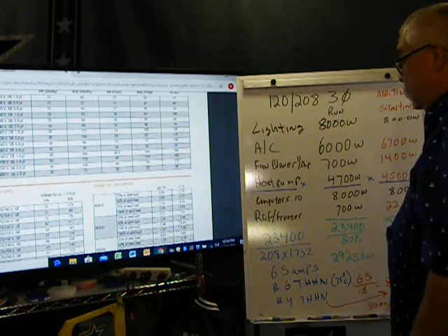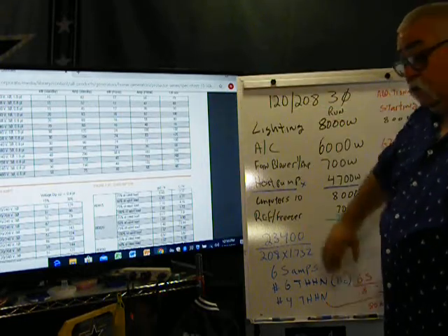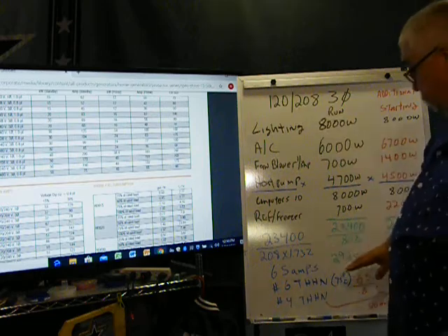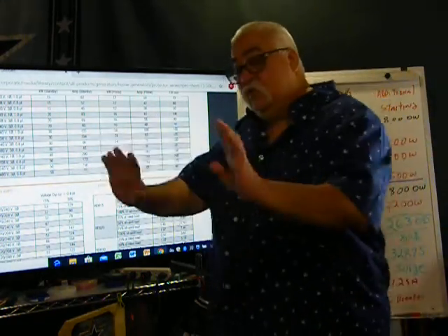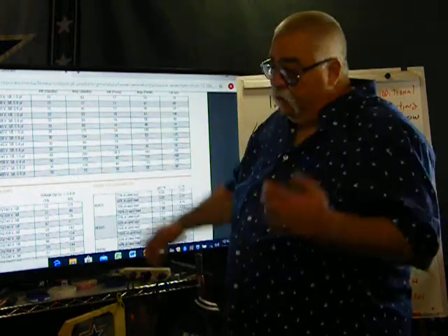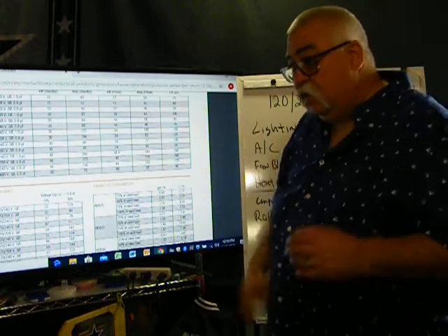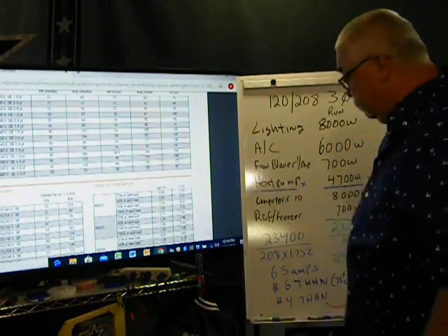I'm allowing for future expansion, but according to this, I'll have to size it as the amperage. Don't look at the wattage. Don't get confused and say, oh, I need a 30. Look at the amperage. You can always come here. Okay, this is the correct way of doing it: you look at the amperage of the generator. Why? Because generators are going to get that wattage and split it up. So, again, you size it up.